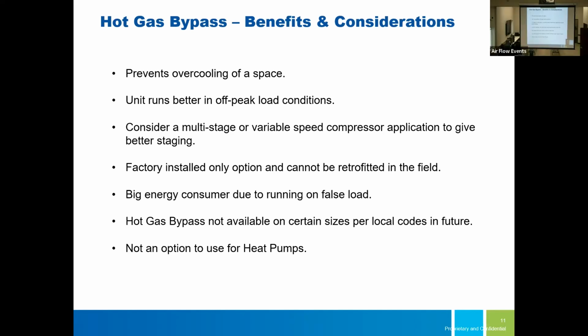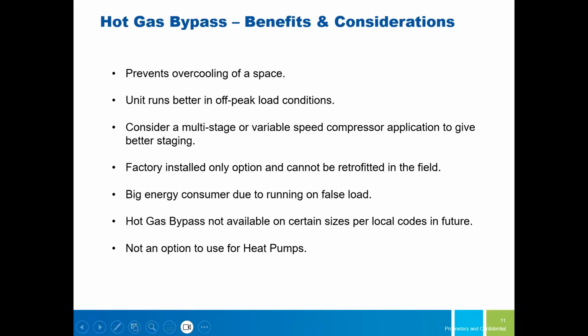Yeah, that works. And then I say this about hot gas bypass: you'll see it here and there, but a lot of people will look at it and say, well, why do I need hot gas bypass? I'll just put a multi-stage compressor on my unit, or a variable speed compressor, right? Wouldn't that do the same thing? Because now you can match the load to exactly what you need. You'll save energy, you can passively dehumidify, because you're cooling all the time, and if your compressor can ramp down to whatever the load is, you never have to worry about any of that. You don't need hot gas bypass if you do that, right?